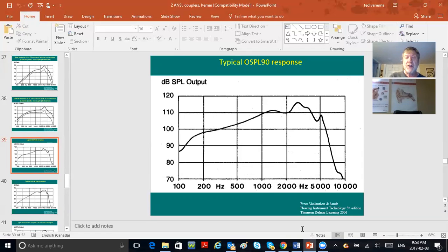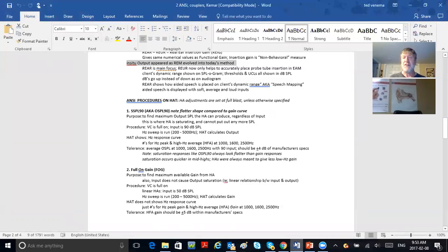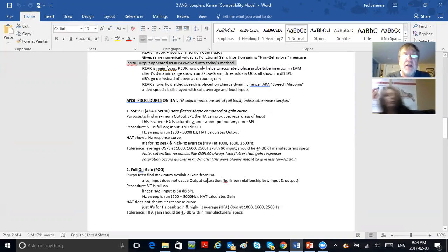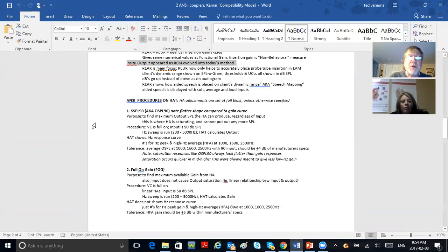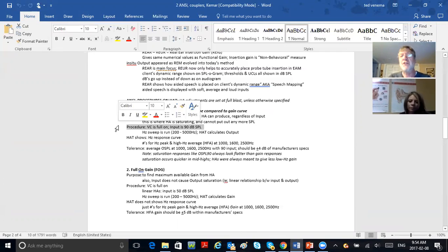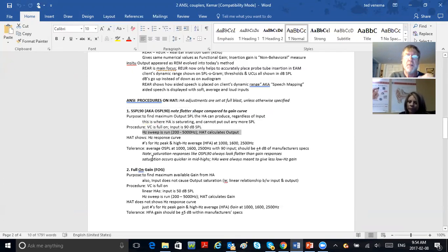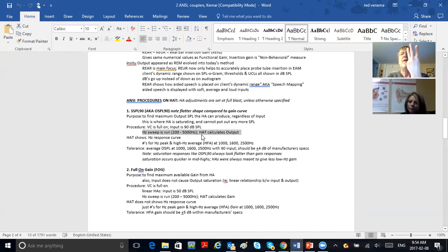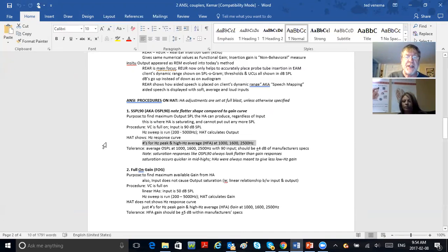The purpose of OSPL 90 is to find the maximum output SPL that the hearing aid can possibly produce regardless of the input—this is where the hearing aid is saturating and can't put out any more. The procedure: volume control full blast, input 90 dB SPL, and a sweep tone is run between 200 and 5000 Hz. The hearing aid test box calculates the output, and you see three things that you need to memorize.